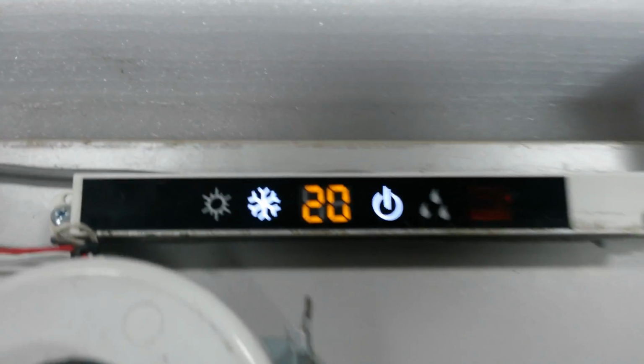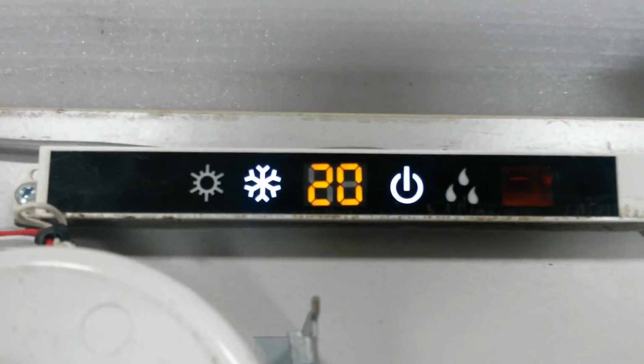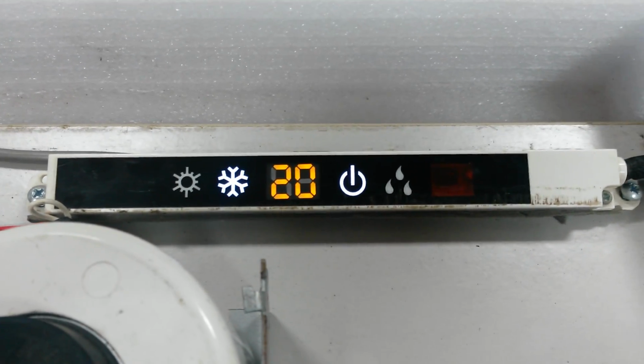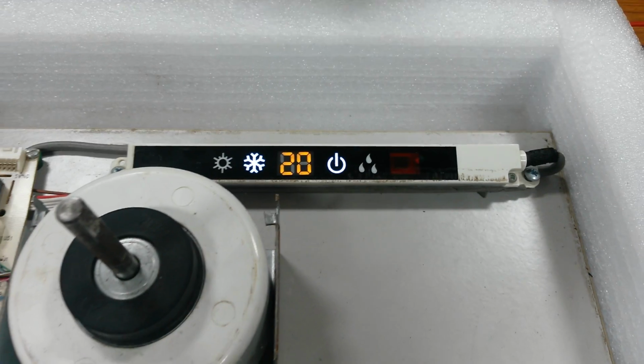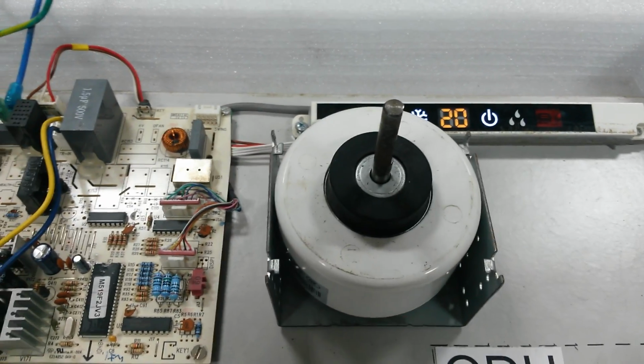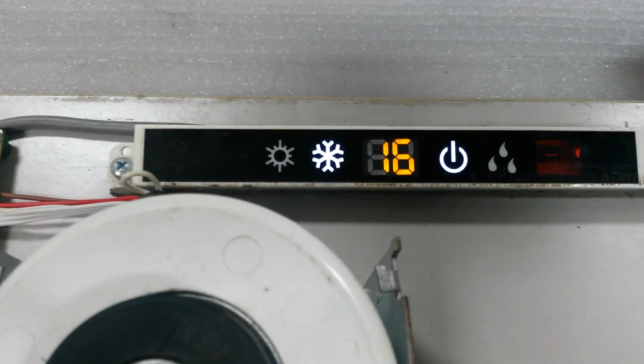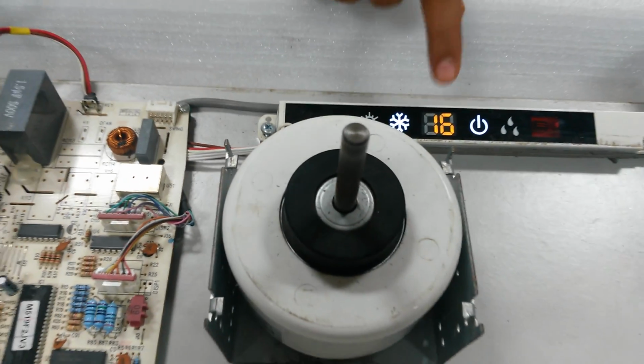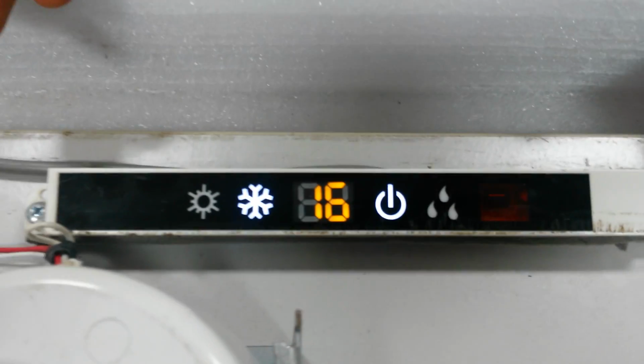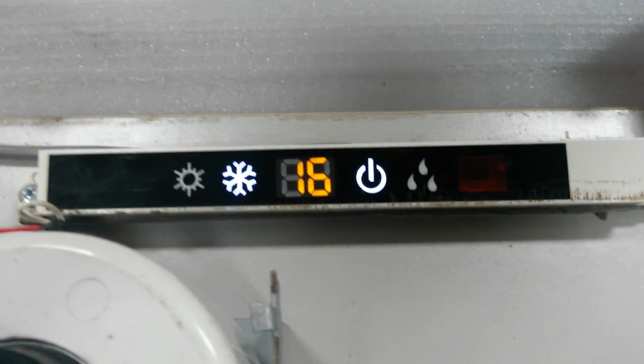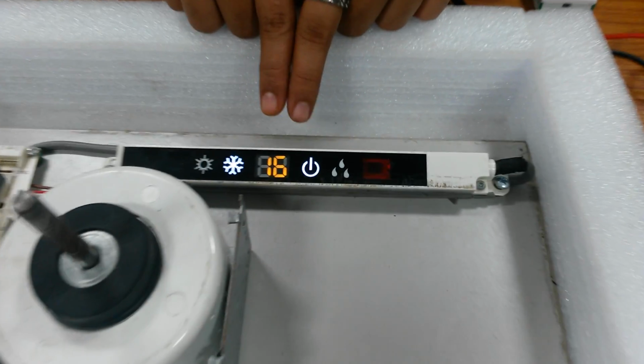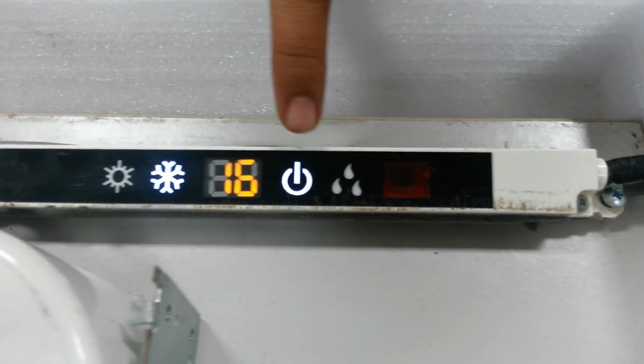When we start this AC at whatever temperature we have set, since the room temperature here is very cool, my compressor will not start. To help it take a start, I will reduce the temperature further. Normally 16 degrees Celsius is not advisable for human comfort, but since my ambience right now is an air-conditioned room and I want my compressor to start, I am keeping it at 16 degrees Celsius, power on in cool mode.